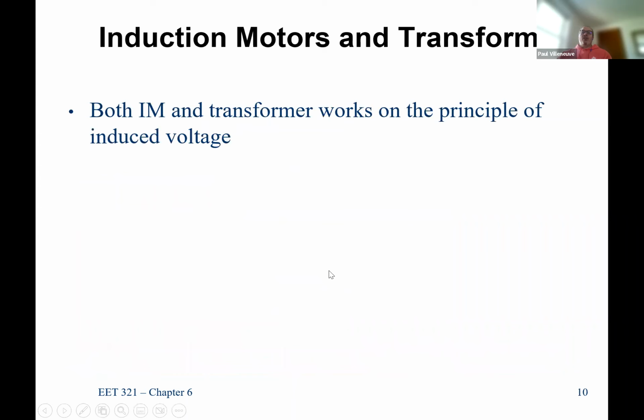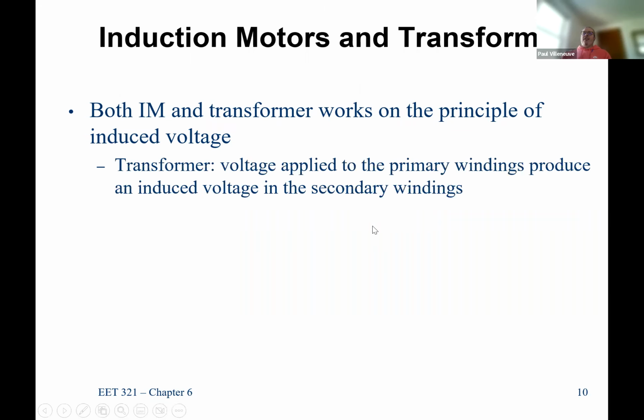All right. So Mort was correct. An induction motor and a transformer are exactly the same thing. The difference is that in a transformer, we apply a voltage to our primary windings and get an induced voltage in the secondary windings. And we take that induced voltage and send it on down the pike to do whatever it needs to do. So a transformer has to have a load to be able to move power through it.